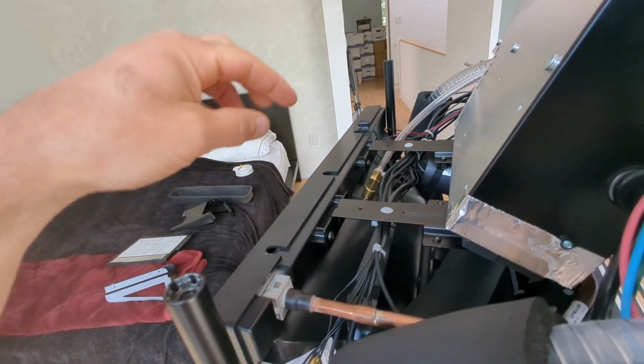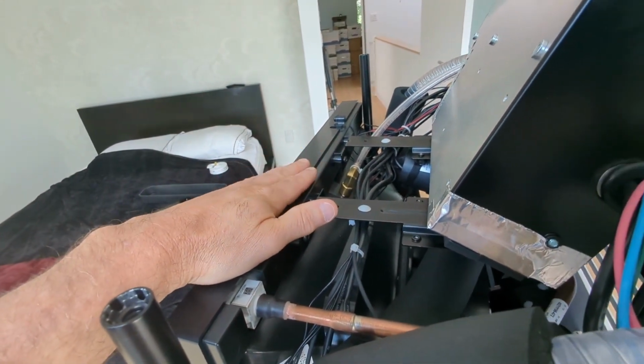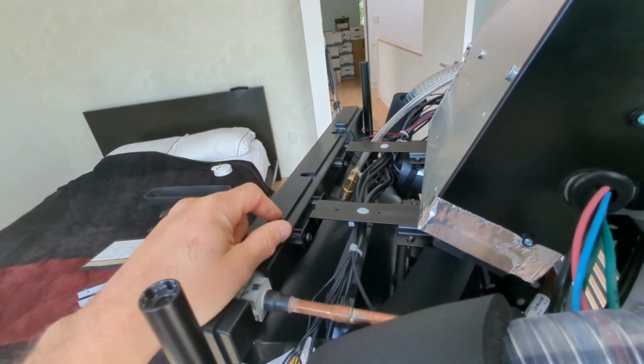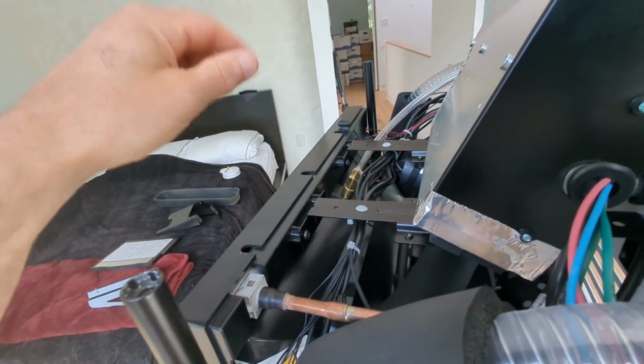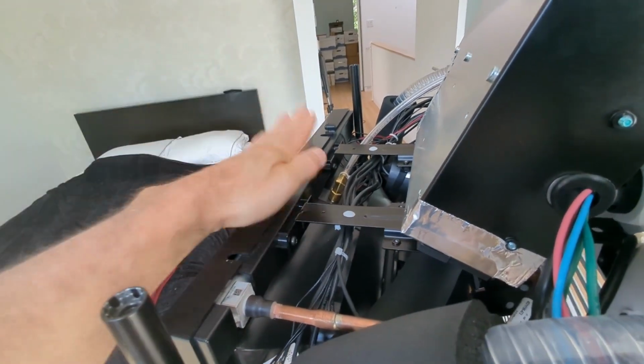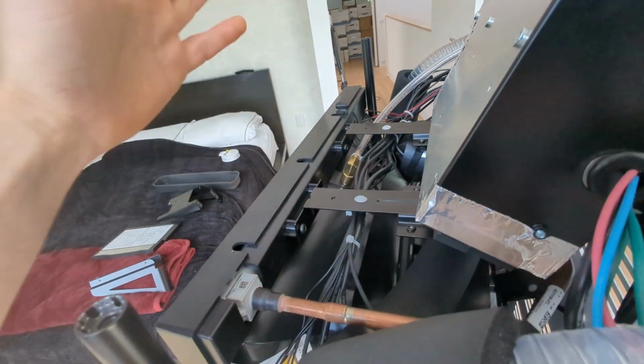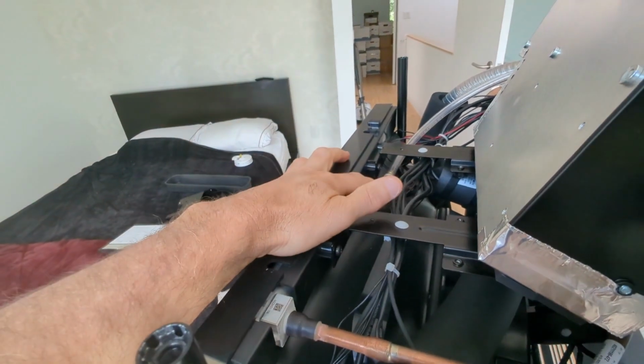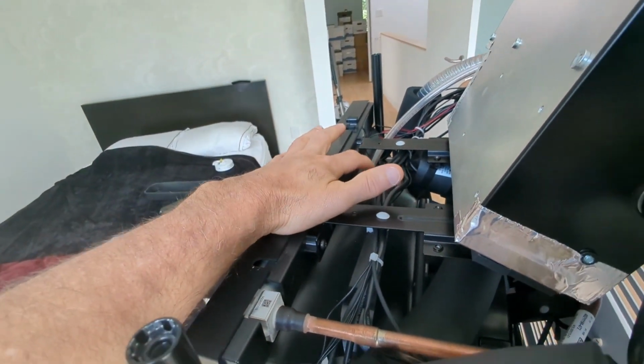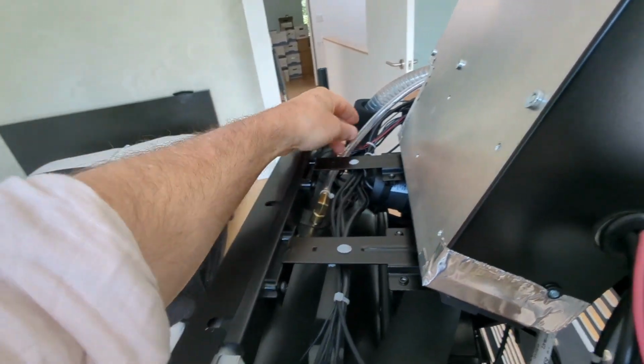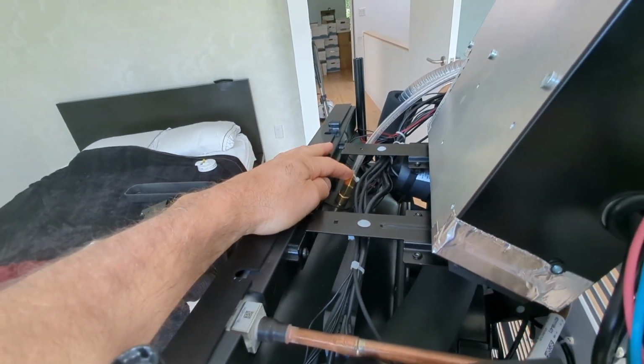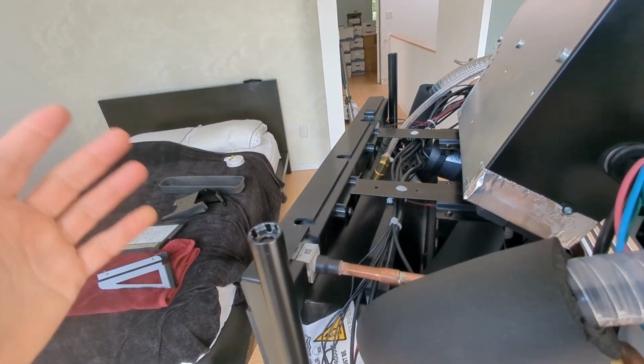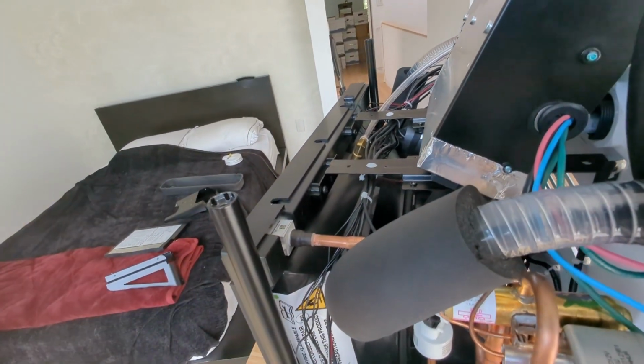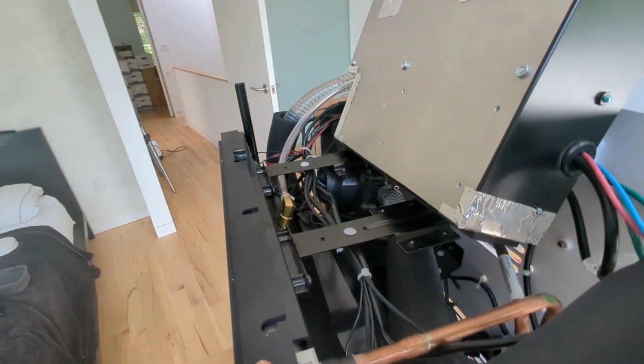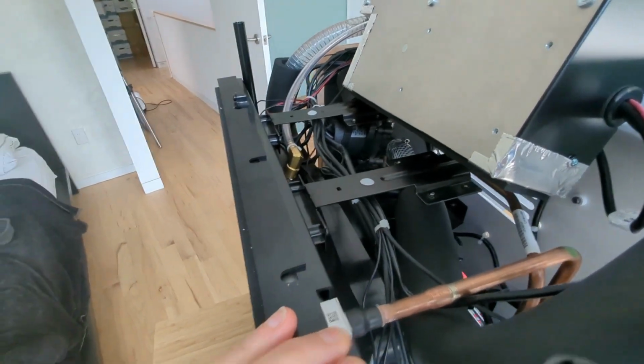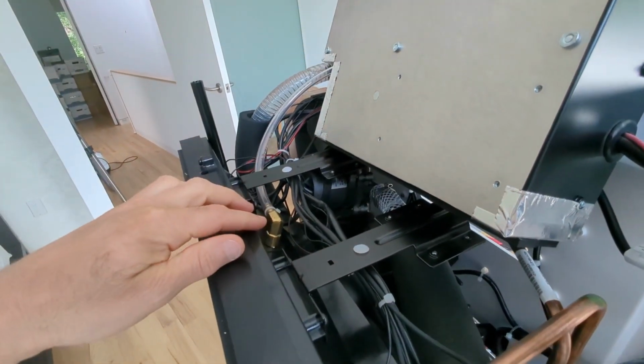And some places actually require you to have condensate management like that. Notably the New York City Housing Authority, which I think that they're trying to get this unit into, so they really had to do that. I do think you take a hit on efficiency though. I think it's slightly more efficient to use that really ice cold condensate water to subcool the refrigerant as it comes out of the condensing coil, but I'm not sure about that. If you know the answer, if you've done the calculations or really measured it, let me know. Curious to know which is more efficient.